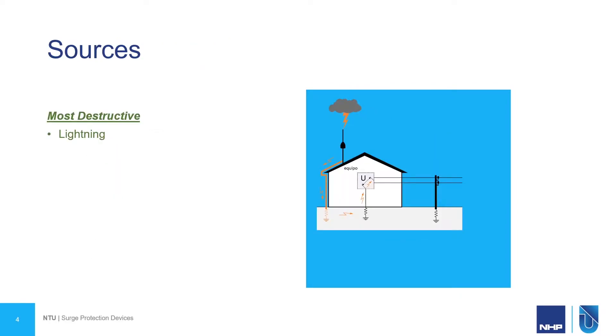So where do these surges come from? Well, the most obvious and certainly the most destructive is lightning. In this case, the building is protected by a lightning rod that conducts the lightning energy down to earth. The problem that causes is that it raises the local potential of the earth above the system voltage, and hence a surge actually enters via the earth and causes damage.